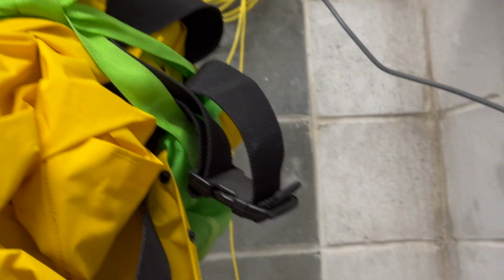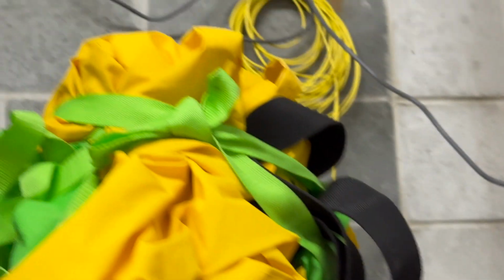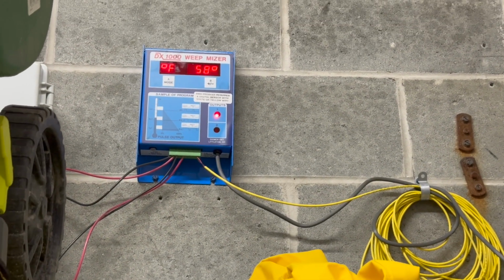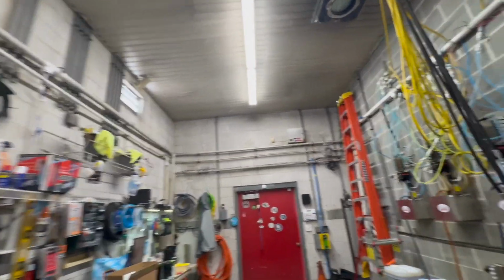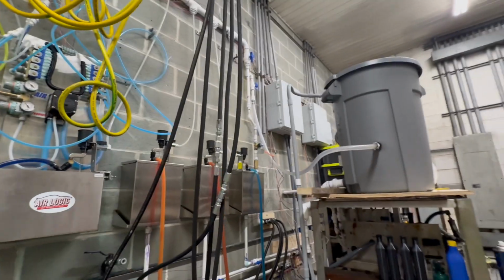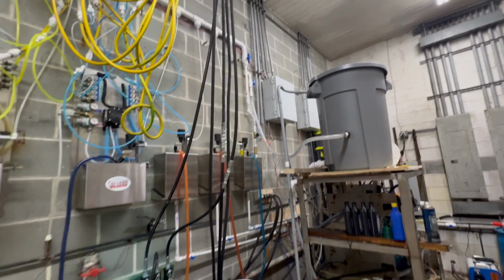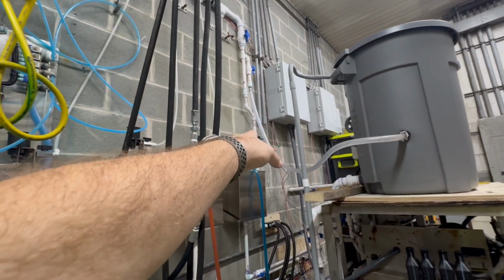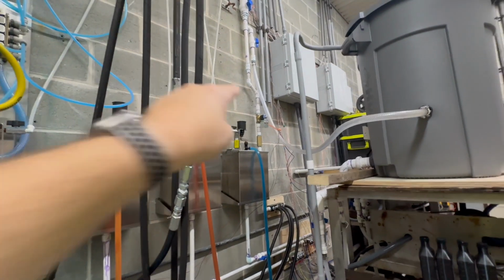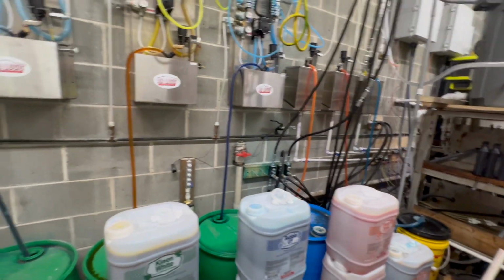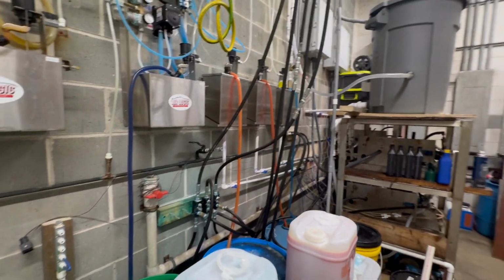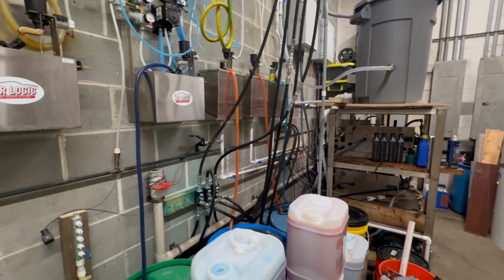That yellow cord is actually a temperature probe that goes out the back wall. The weep miser monitors the temperature, and when we get below a certain threshold, I believe for me it's 39 but I've got it set to 38, it will start cycling water through it. It flips this valve, actually turns the valve off to let water flow, which flows down through these black hoses over through here, and independent of everything else, a little bit of water leaks out of the guns in the bay. It's sending water down the drain, but it keeps things from freezing, and that's more important.